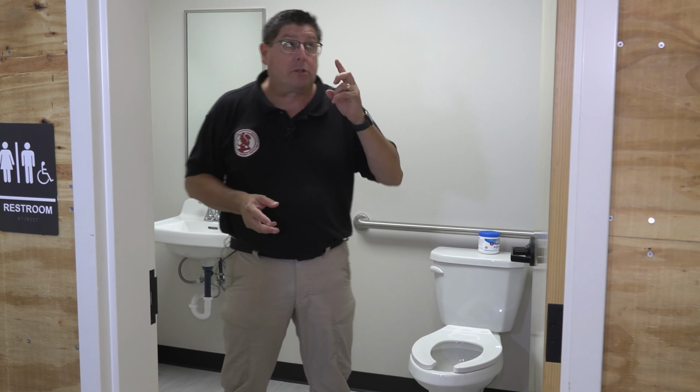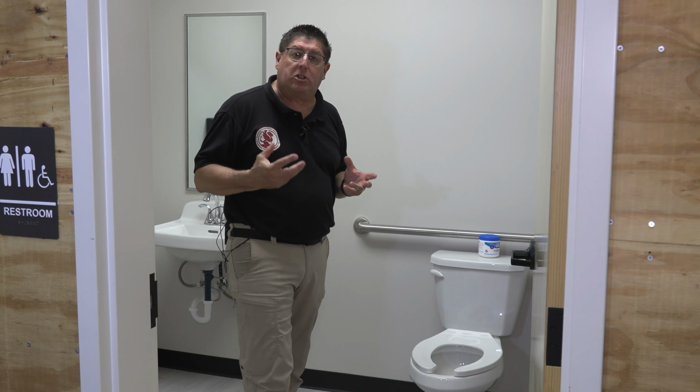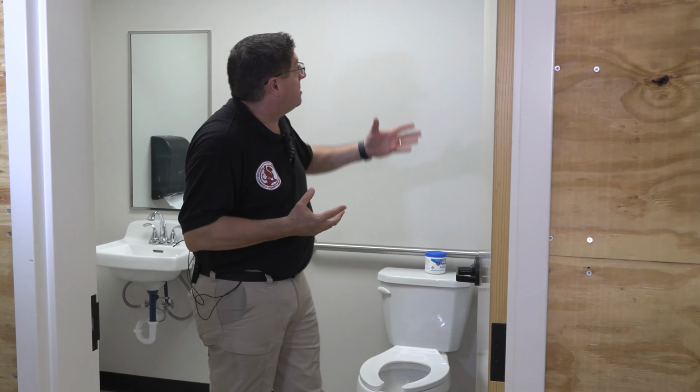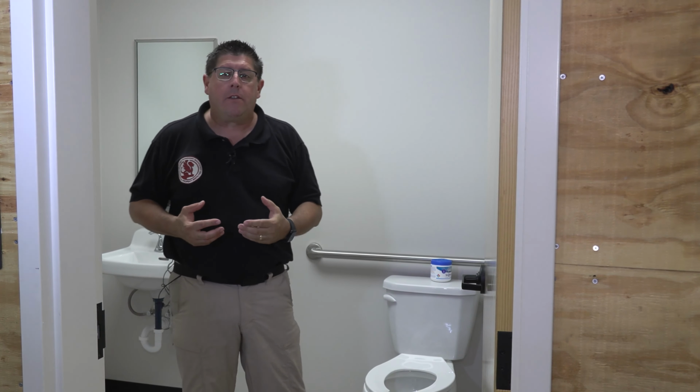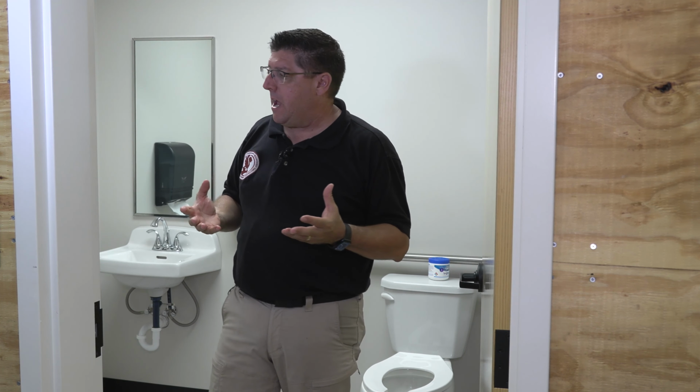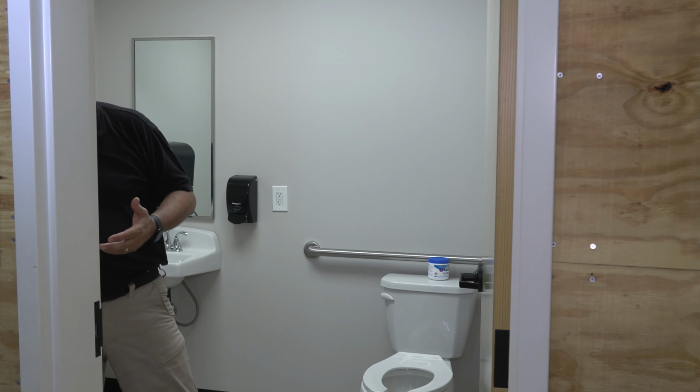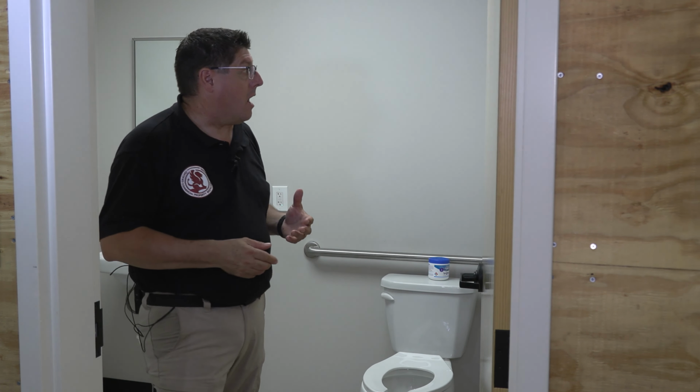Then next, we want to make sure there's some form of exhaust. Bathrooms can become unpleasant over time depending on usage. And in this particular case, we do have an exhaust. The exhaust could be local, which this one is, or it could be a major plumb system up through a vent, all the way through the roof where there's a static vent on the roof. In this case, this particular fan operates on a motion sensor, and then it would shut off over a period of time.